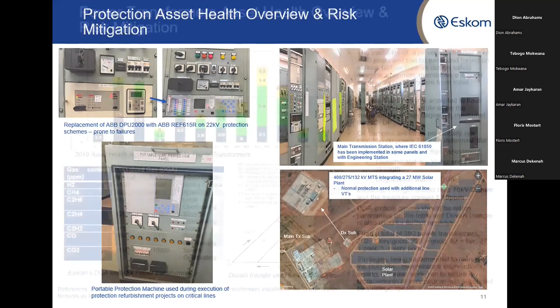Looking at the other assets, after the protection assets, at the plant assets, which now focuses on transformers. You can see that the life of these primary plant assets, transformers, is quite long. We had estimated around 40, but with good designs, operating them well and maintaining them well, we are seeing transformers living in excess of 56 years. And we know that as we do oil samples on a periodic basis, what is quite important that will determine the useful life of a transformer is the DP, which is the paper. Once the paper is faded or is degraded, you know that the transformer will have to be replaced.